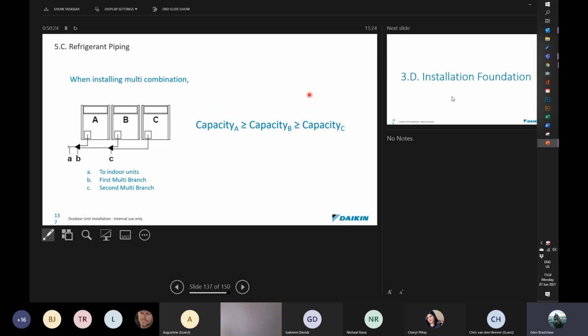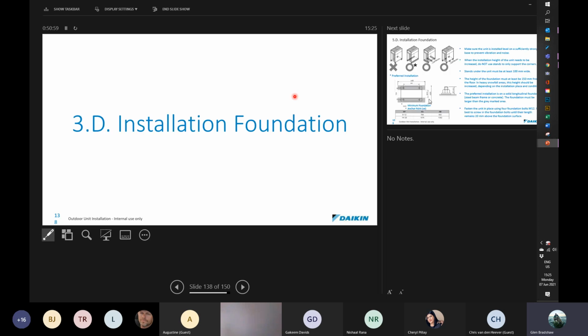All right, something else to remember when placing condensers down on an installation is that the highest capacity is where the piping enters, okay, and it scales down. Capacity B being less than A and C being less than B. Okay, so there's how they try and depict it. Don't go and put the smallest unit in the front and the biggest unit at the end. Don't do it that way around. You will end up having to change it. All right, so just be aware of that. Okay, so capacity, the way it slides down is also very important.